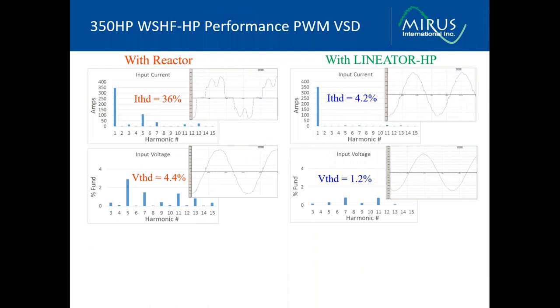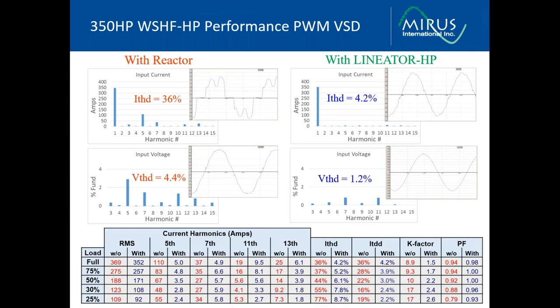In this slide, we show some factory tests of a filter. This was applied on a 350 horsepower drive, equipped with a line reactor. So in normal operation without the passive filter installed, there was 36% current distortion. That current distortion introduced 4.4% voltage distortion on the distribution bus. When we switched in the passive filter, you can see the current became much more sinusoidal. Current distortion was 4.2%, and that reduction in current harmonics flowing through the power system lowered the voltage distortion to 1.2%.